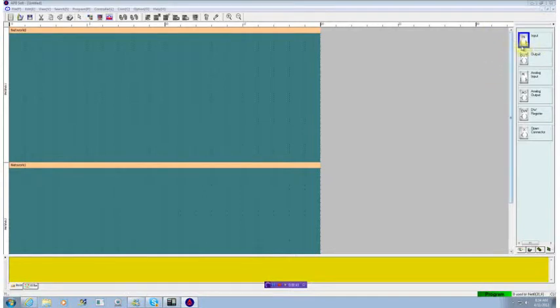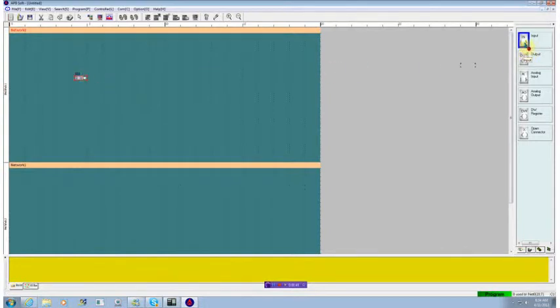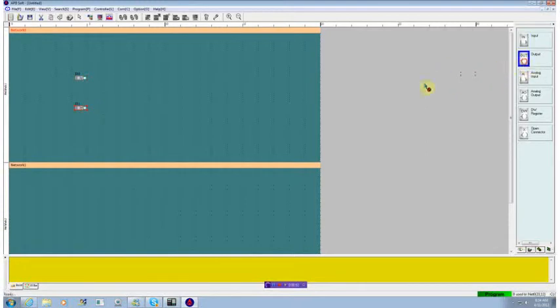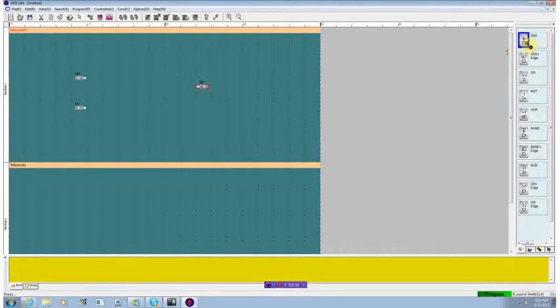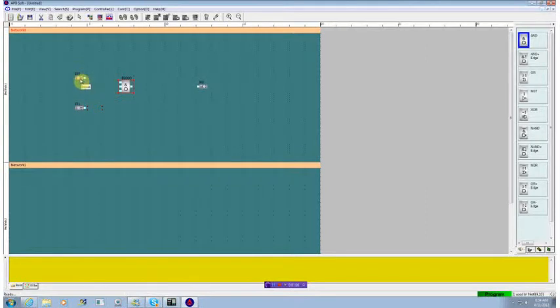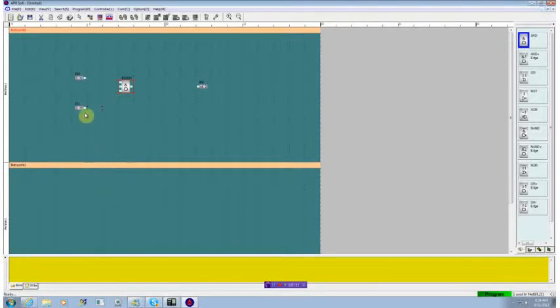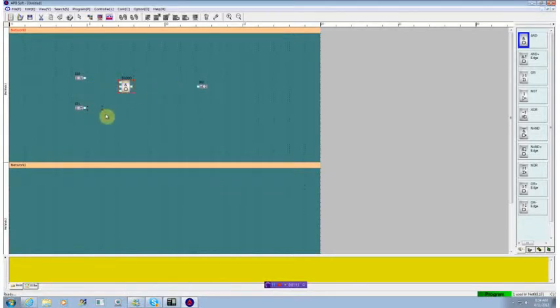We want to take a look at a motor control system. So we're going to put in a couple of inputs here. Two inputs and an output. And we want to look at some combinatorial logic to begin with. So we'll add in an AND gate. All we want to do is say if this input and that input's on, then we want to turn on the output. In conventional ladder logic, we'd show that as a series of contacts, two in series. If both contacts are closed, then the output would be on.